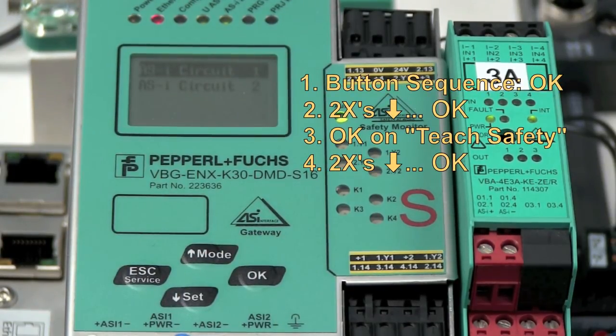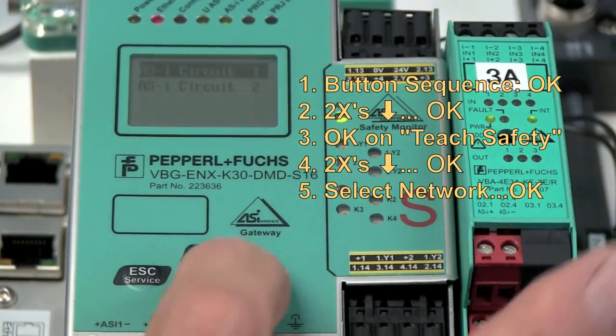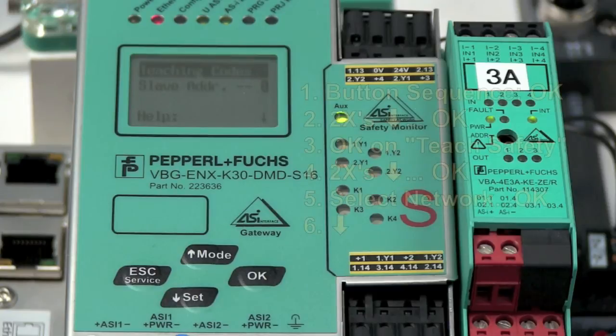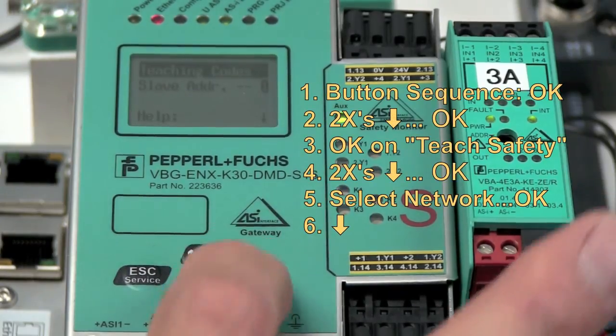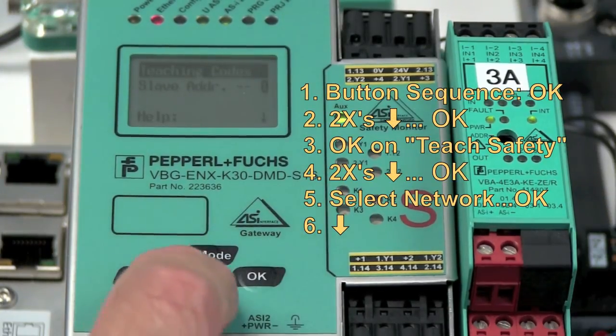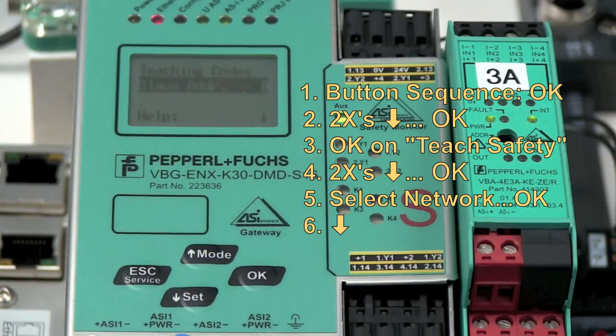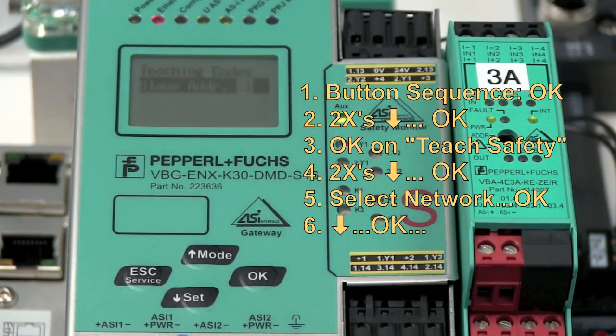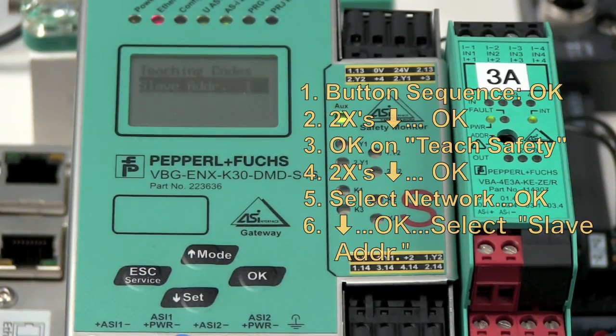The failed module and the replacement module were on network 1, so I OK this one. And then I come down to slave address, hit OK, and with the up and down buttons, I will select which address I will have to reteach.